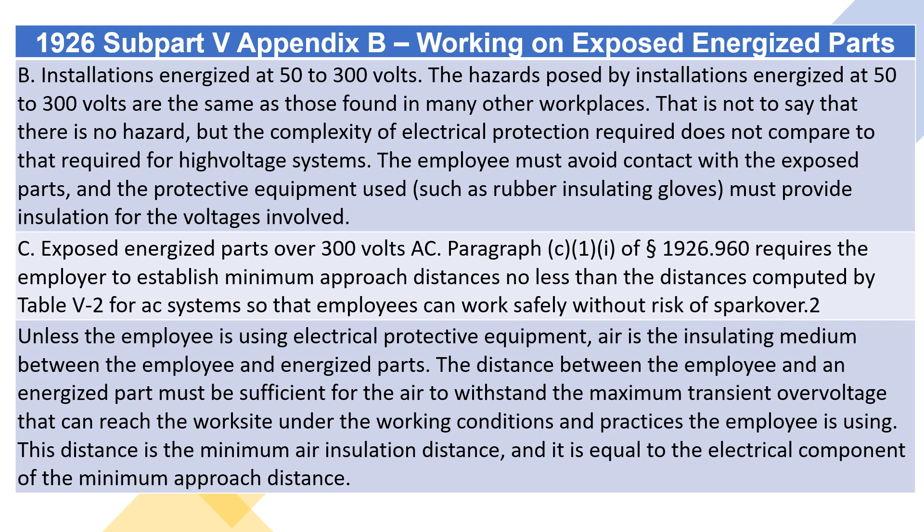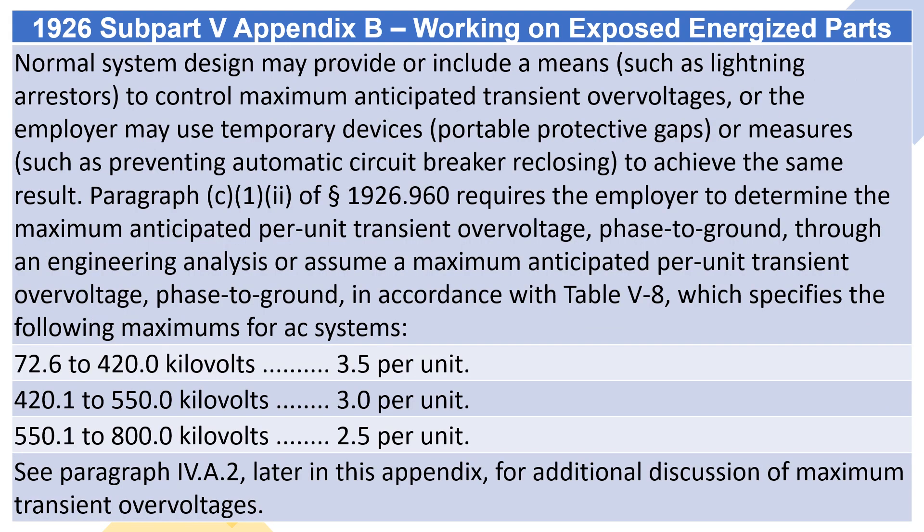Unless the employee is using electrical protective equipment, air is the insulating medium between the employee and energized parts. The distance between the employee and an energized part must be sufficient for the air to withstand the maximum transient overvoltage that can reach the worksite under the working conditions and practices the employee is using. This distance is the minimum air insulation distance, and it is equal to the electrical component of the minimum approach distance. Normal system design may provide means such as lightning arresters to control maximum anticipated transient overvoltages, or the employer may use temporary devices, portable protective gaps, or measures such as preventing automatic circuit breaker reclosing, to achieve the same result.